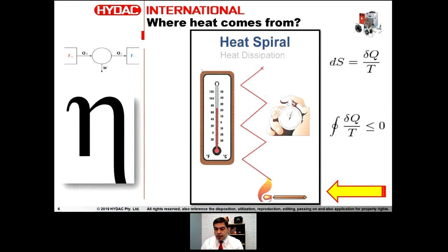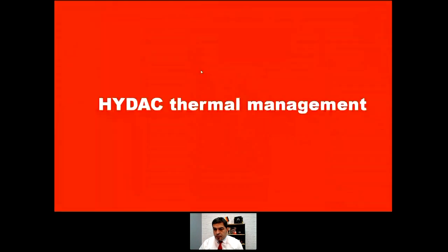Can we cool back to the origin of this spiral? Not really, because entropy is growing and this is not a reversible process. The right target temperature relates to viscosity — the Greek letter eta. The best cooling point is where we size the cooler for the right viscosity: around 30 centistokes for some applications, 60 centistokes for others, depending on the machine and application.